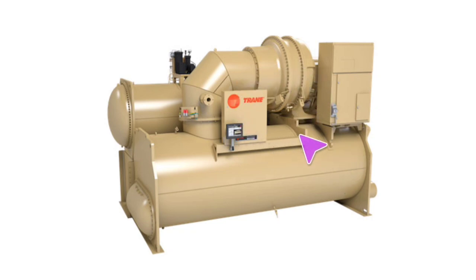Surge is when there's too much lift on the system and the impellers cannot continue to move that refrigerant. It literally builds so much back pressure on the impellers that it back feeds refrigerant back through in reverse direction through the compressor, which is extremely damaging to the bearings in particular. They just do not like that, and a compressor is only going to take so much of that before it just stops.